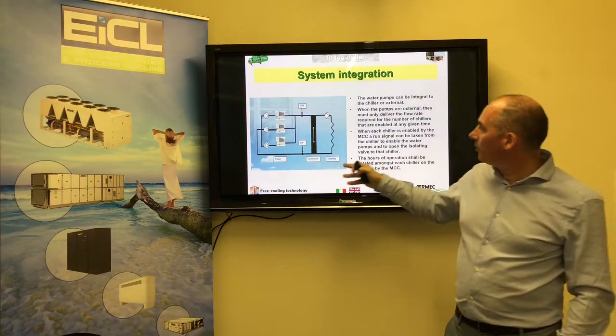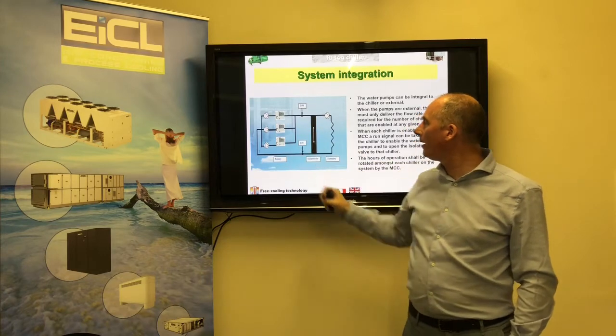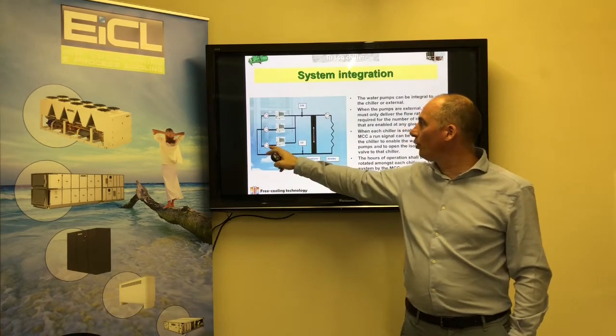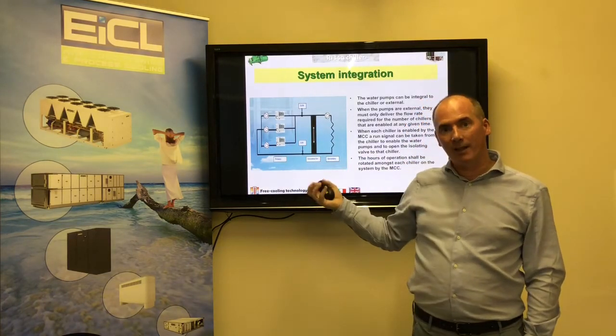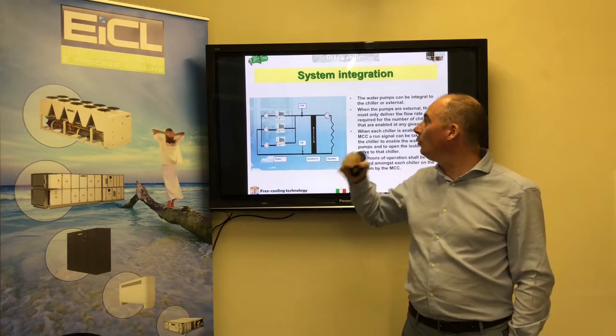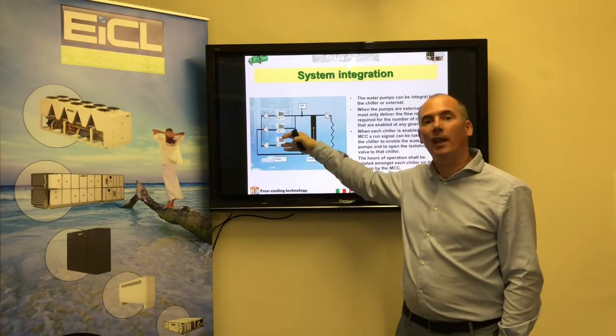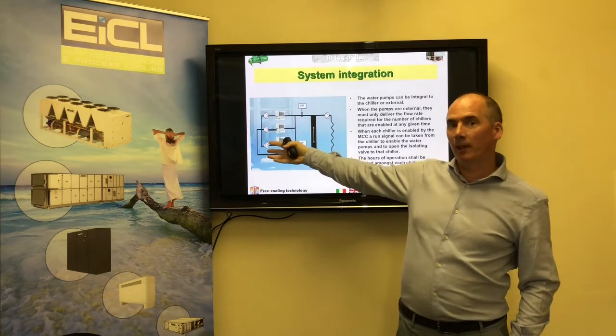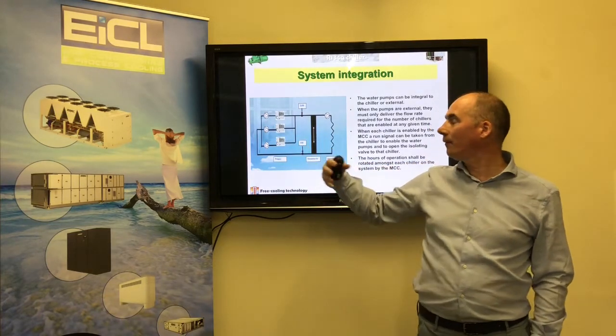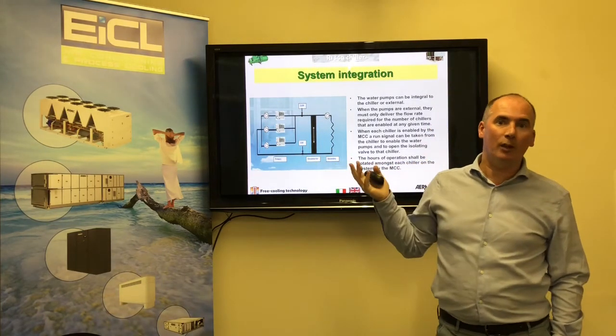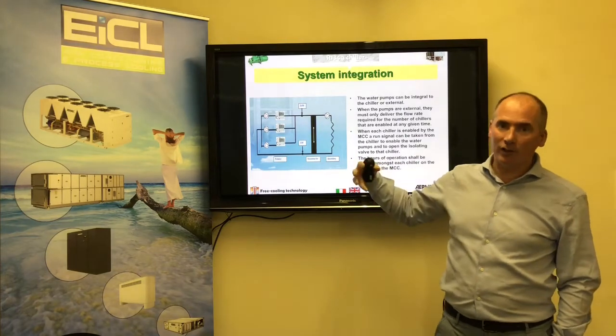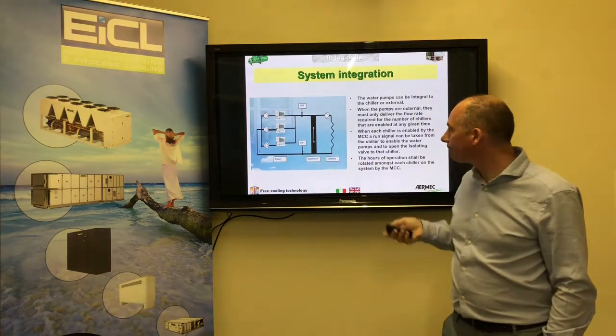So this is simply how you would have your system. Chillers connected in parallel. Obviously you need to run the pump for the chiller that's on. So you would have an additional flow rate when you enable that chiller, but you might have a couple of kilowatts of a pump. But if you consider you have chillers with a couple of 100 kilowatts of absorbed power, you can see the efficiency is quite good.